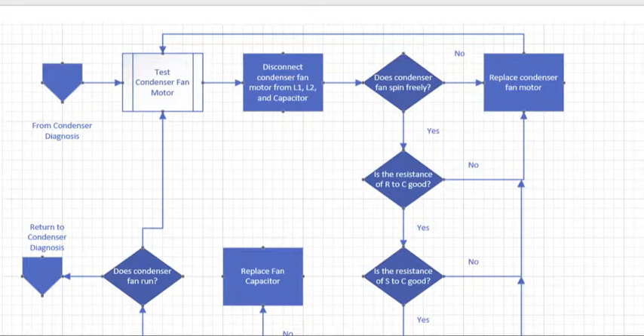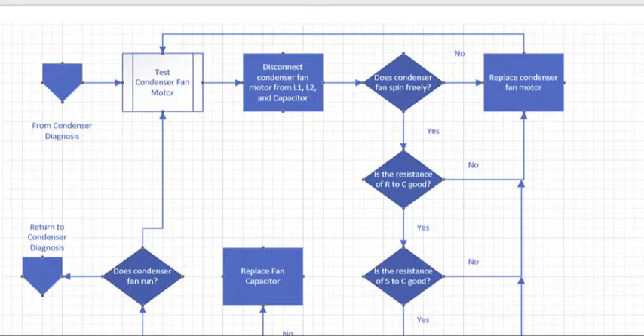Most of these are now sealed bearings. Putting oil on it doesn't help. And condenser fans have to spin freely or you don't get enough airflow and proper airflow across that coil. Also, if a condenser fan motor is not spinning freely, as it heats up, it's just going to get worse. So it's very likely the thing could be working properly while you're sitting in front of it. Pressures look good and everything. But three hours after you leave, you're going to suddenly have a very upset customer because that condenser fan motor has heated up and stopped working.